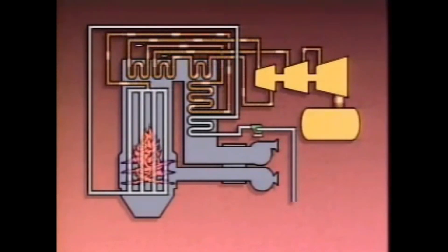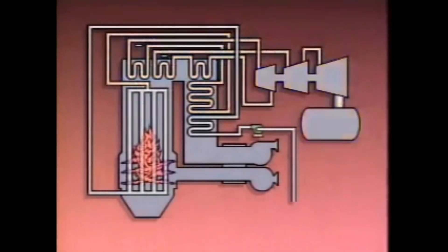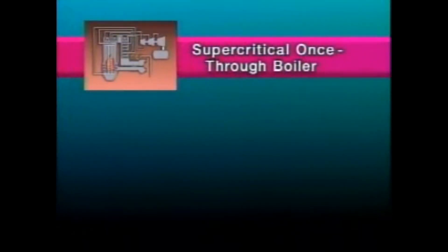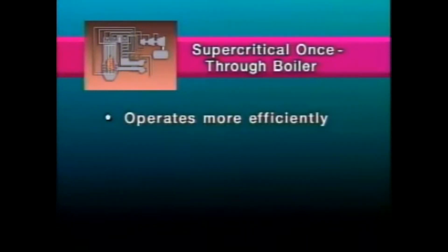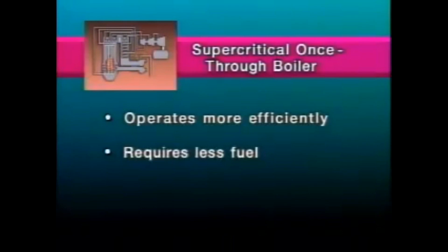The components in the steam flow path are generally the same for supercritical boilers and subcritical boilers. The main advantage of a supercritical once-through boiler is that it operates more efficiently than a subcritical boiler that has to recirculate water in the process of producing steam. A supercritical once-through boiler requires less fuel than a drum-type boiler of the same size to produce the same amount of steam.